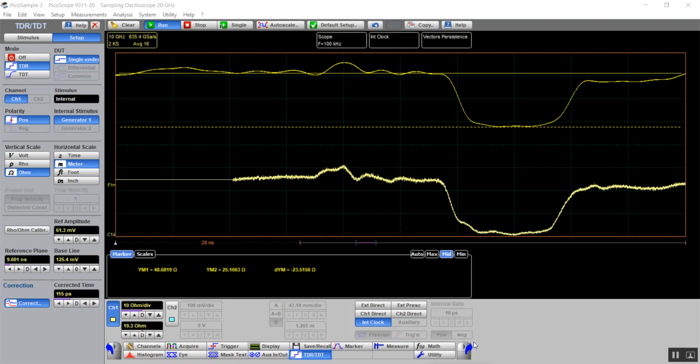The instrument provides a fast gain calibration and correction procedure, which easily allows you to change the rise time of the corrected step for TDR or TDT on each of the channels. By using correction, the results become more reliable, more repeatable, and accurate. In addition, performing a correction allows the instrument to simulate stimulus steps with different effective rise times. This allows you to view the effect of actual signal rise times on the magnitude of reflections from the discontinuities.